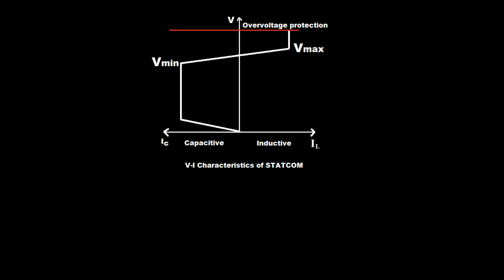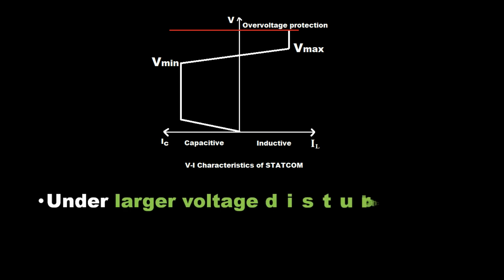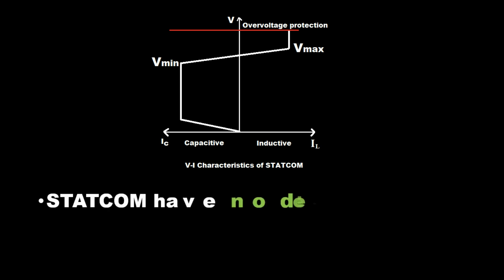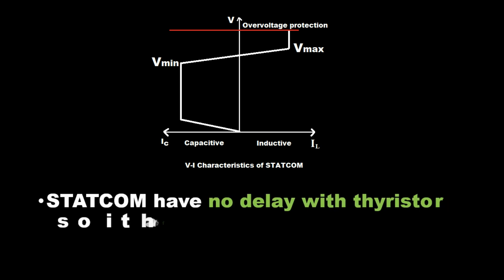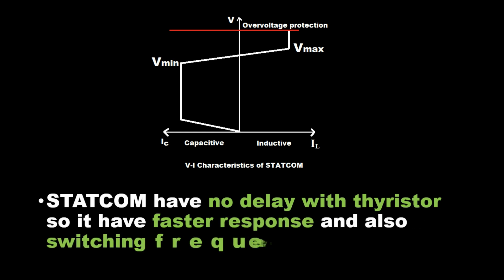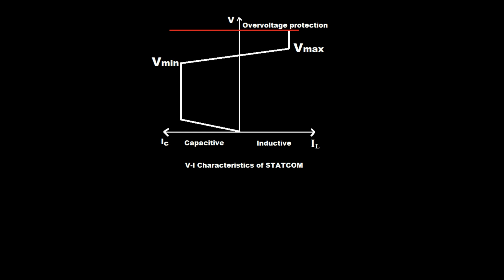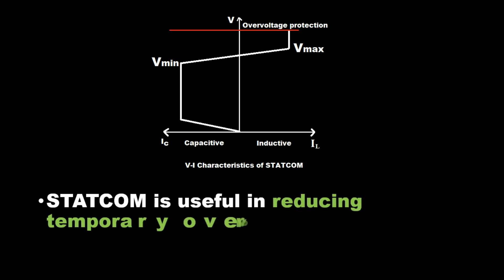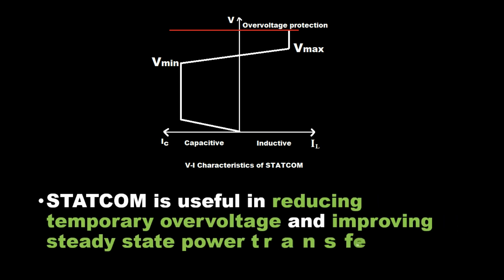Under larger voltage disturbances, STATCOM is more useful. STATCOM has no delay with thyristors, so it has a faster response and higher switching frequency. It is useful in reducing temporary overvoltage and improving steady-state power transfer.